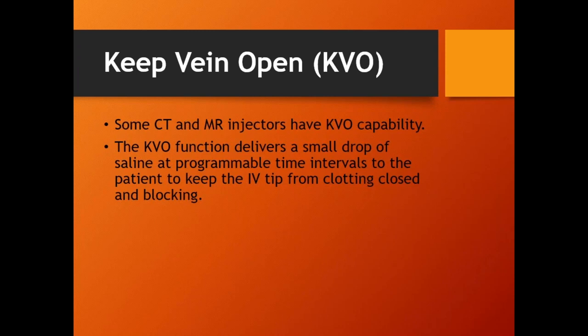Now, not all CT injectors do this, but there is a function that a lot of them have, and it's called KVO. KVO stands for keep vein open. Because there can sometimes be a long pause between, I don't mean pause like 5 or 10 seconds, like minutes go by between actual contrast injections. And the tip of the IV needle can actually form a blood clot at the tip, okay? So to keep that from happening, they can turn on the KVO feature.